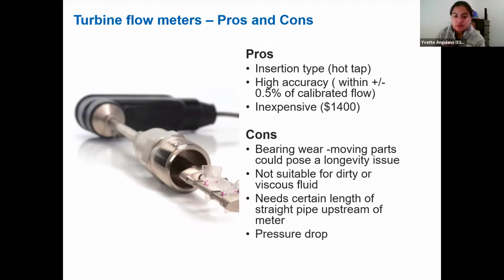A reason you might not want to choose this meter is because it has moving parts. The rotor has to rotate on bearings, and those can wear out. Over time, the meter will become less accurate and unusable. So it's important that when using this device, you have very clean water, and that you're using a media similar to water, not a media that could be too viscous. Otherwise, the meter won't work. You also need a certain length of straight pipe upstream and downstream of the installation of this meter to ensure smooth flow through it. And lastly, anything that's inserted into your pipe system will have a pressure drop.